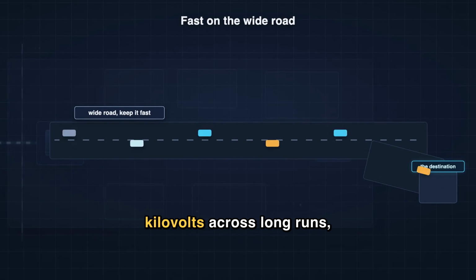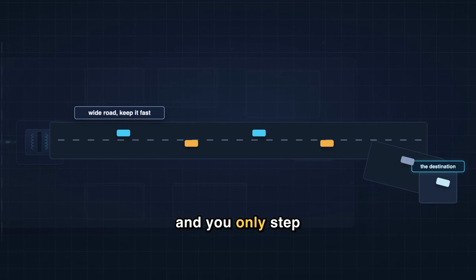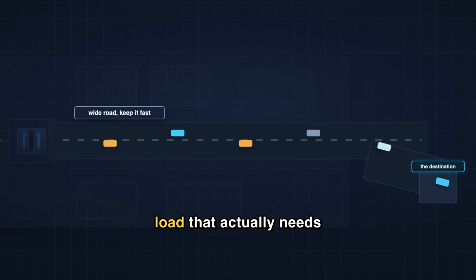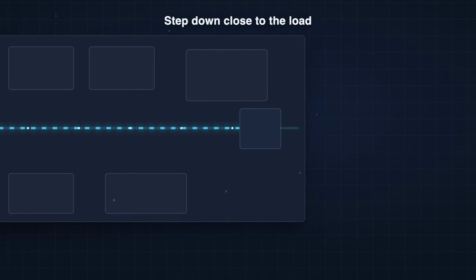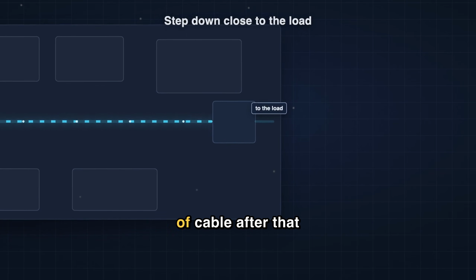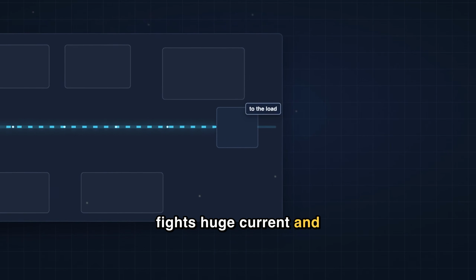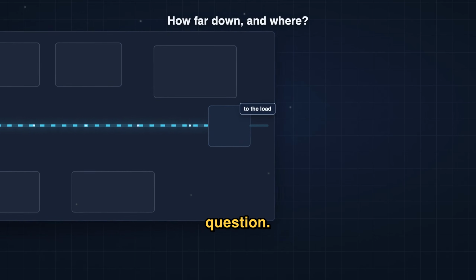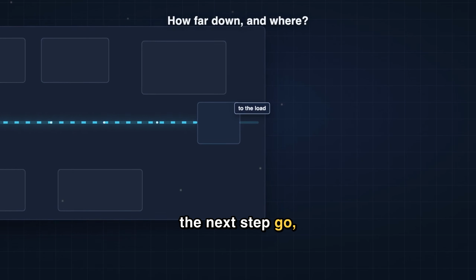You distribute at kilovolts across long runs, and you only step the voltage down when you're close to the load that actually needs the low voltage. Step it down too early, and every foot of cable after that fights huge current and bleeds heat. But that raises a question. How far down does the next step go and where?